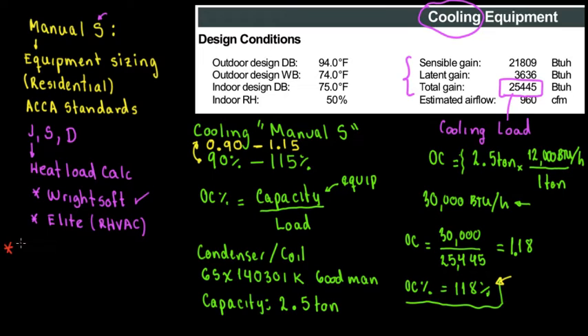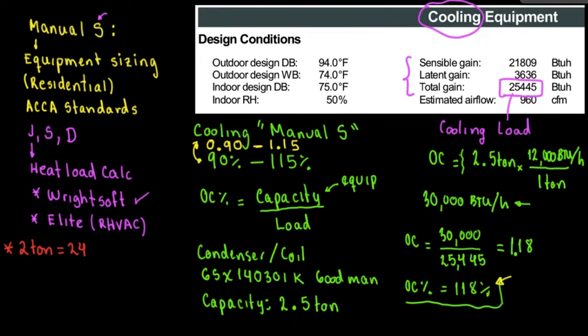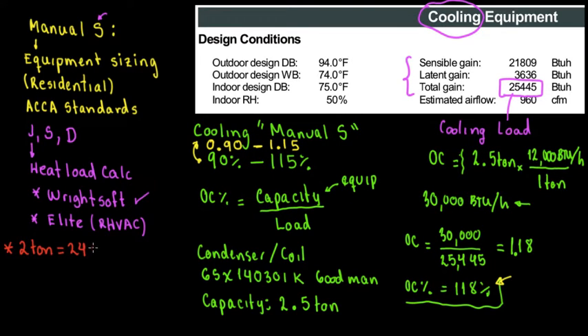So, 2 ton system equals 2 ton times 12,000, that's 24,000. That's 24,000 BTUs per hour. And the load is not going to change. So, the oversizing percentage is going to be equal to 24,000 which is the nominal capacity of the equipment divided by the load. The load is going to be 25,445. So, this is going to give me a total of 24,000 divided by 25,445. So, this gives me 94%.